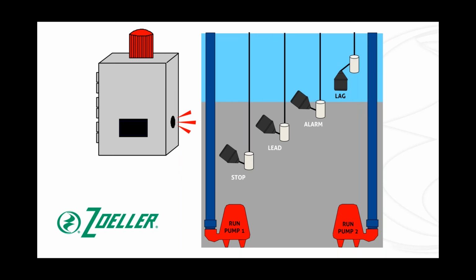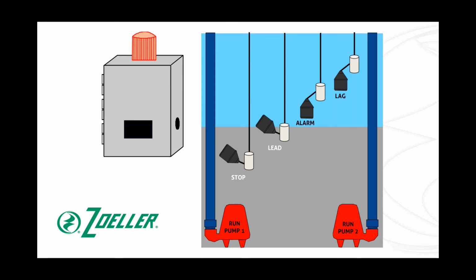So just to finish this off here, with both pumps running now, we begin to make headway on the water flow that was coming into this pit. As the water level drops, our alarm float drops out, and when it does, our audible and visible alarm is deactivated, and the water level continues to pump down with both pumps running together.